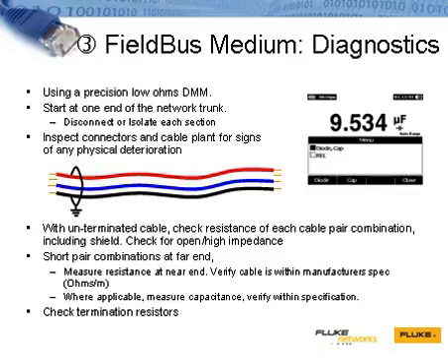David, yes. Essentially, the goal of testing a FieldBus cable is to check for opens and shorts between the electrical signal conducting paths, making sure we test each cable pair combination. Also, for testing purposes, we should think of the copper wire as a source of impedance. Measuring the cable resistance of each conductor, as well as the resistance and capacitance between them, will help us understand the cable impedance. Any impedance mismatch across the transmission path can potentially degrade the encoded signal.